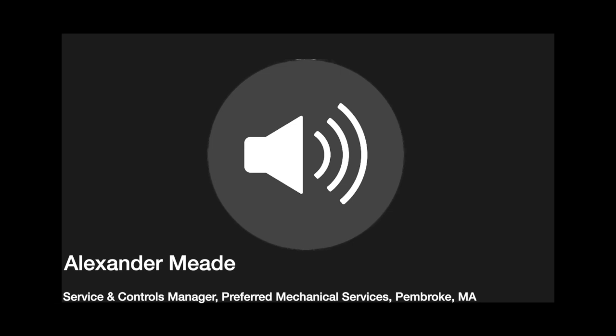unless your rink is very cold, that wouldn't be the case. And an IR gun is pretty inaccurate when it comes to measuring actual temperature. If you talk to infrared manufacturers, and there are white papers that explain this, the best thing you can do with an infrared gun is measure a dark surface as close as possible. So when you use an IR gun, it's good for relative measurement, but it's hard to get an accurate reading on a white sheet of ice with an inch or so thickness on top of a white surface.